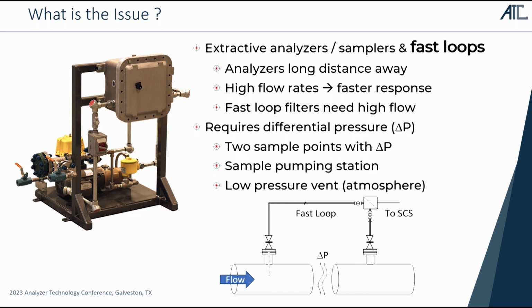And that usually means that we're either going to have process differential pressure available, or we're going to have to put something like a sample pump in, or we're going to put in a low pressure vent. We're going to vent to a flare header or maybe atmosphere. We'd like to find a way to be able to create fast loops without having to meet all those requirements.